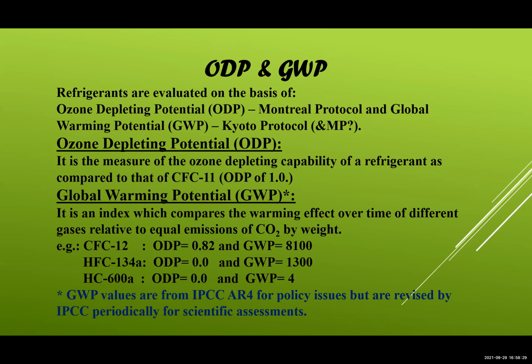So just to give an idea, the ODP is a kind of a relative term. It's not an absolute value. It is only determined with respect to another refrigerant. So we call it ODP. It means ODP of CFC11 is kept as a standard ODP of 1. So any value you are quoting for other refrigerant, it's with respect to R11.